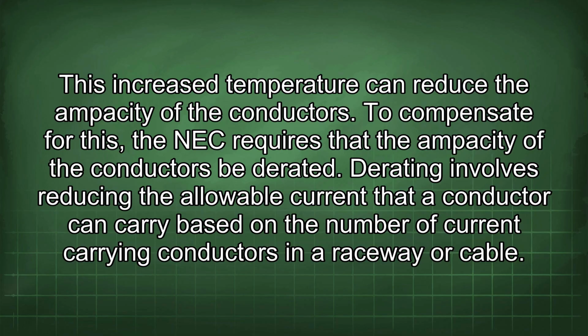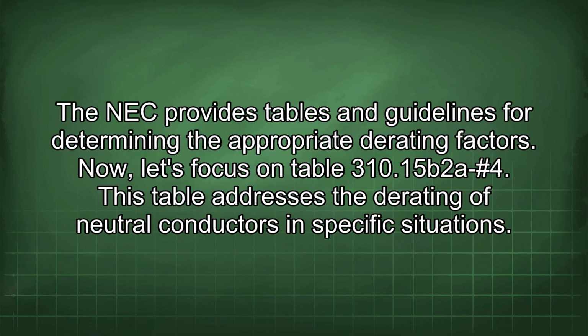To compensate for this, the NEC requires that the ampacity of the conductors be derated. Derating involves reducing the allowable current that a conductor can carry based on the number of current-carrying conductors in a raceway or cable. The NEC provides tables and guidelines for determining the appropriate derating factors. Now, let's focus on Table 310.15(B)(2)(a)-#4. This table addresses the derating of neutral conductors in specific situations.